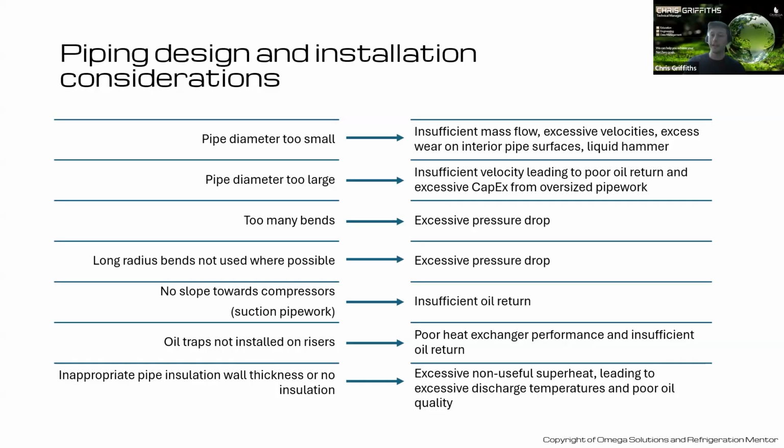Exactly. The ideal perfect conditions never exist, and the ideal design never exists. Particularly with pipe sizing, the actual correct size may be halfway between the 2 pipe diameters which are actually widely available. Manufacturers aren't going to manufacture a huge run of specialist pipework for such a small application generally, unless it was a very, very specific design with a budget to do so. And we have to work within budgets and constraints, and that's what makes it fun engineering rather than just what the numbers spit out. What can you do?